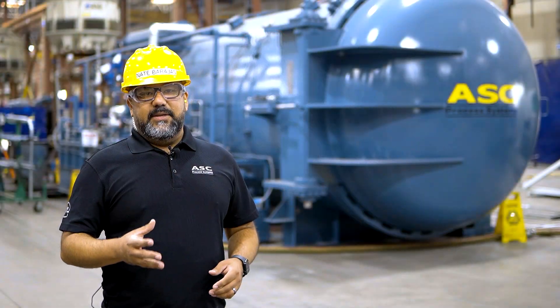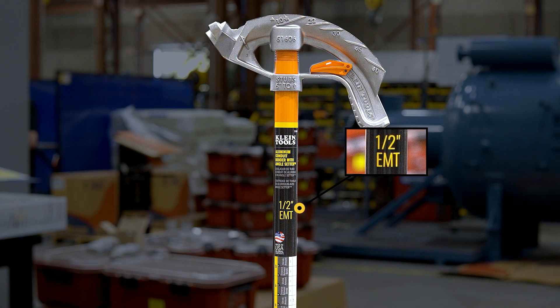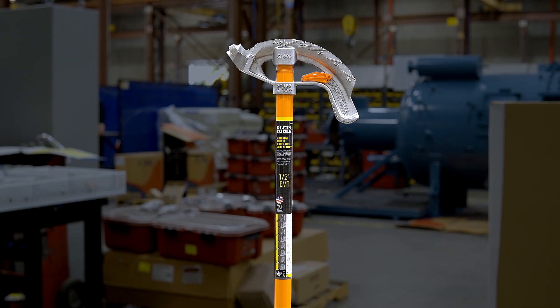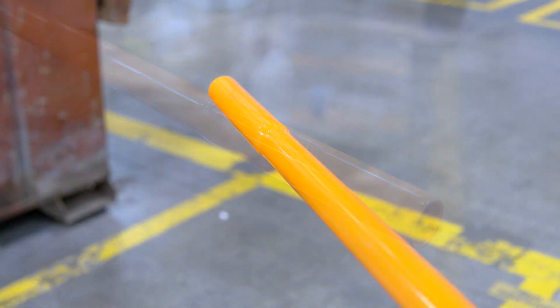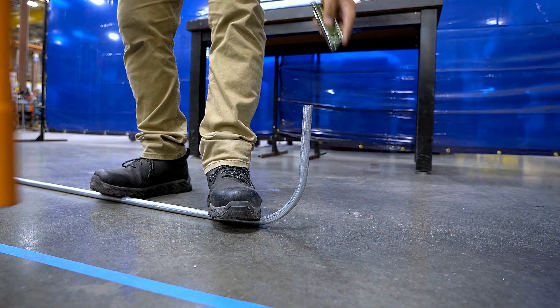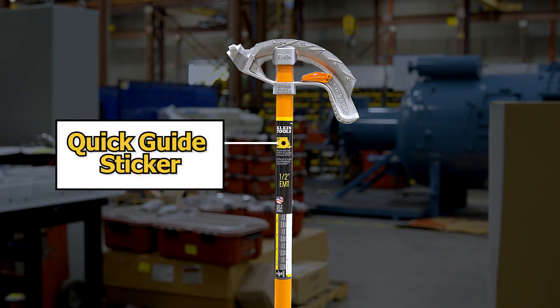Let's go over the anatomy of this tool. Keep in mind we are referencing a 1/2-inch Klein Tools bender; however, other conduit benders should have similar markings and functions. Here is the handle. At the bottom of the handle, you will notice a flared end. This comes in handy when making slight corrections if you overbend or underbend your conduit. On the handle is a sticker — a quick guide for conduit types and sizes that can be used to help calculate offset bends.